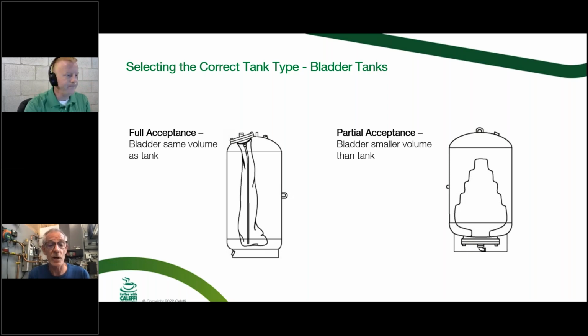So it adds a lot of cost because people say, well, you put a stamp on it and you're charging me a lot more money, but there's a lot involved with that. The steel, the nuts, the bolts, everything that goes into the installation has to be recorded right back to the steel mill that made that bolt or nut or whatever. So there's paperwork involved. The welder has to be certified. So it's not somebody just putting a different label on that day and raising the price. There's a bit involved with any ASME vessel. So just know that compressor tanks, anything, they all fall under some pressurized vessel listing with ASME.